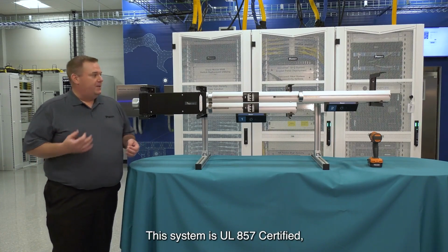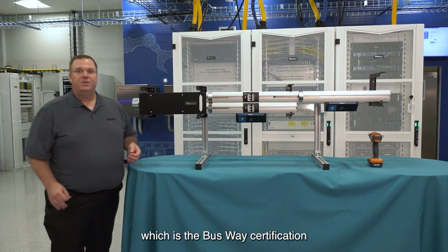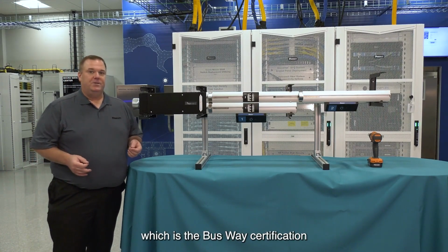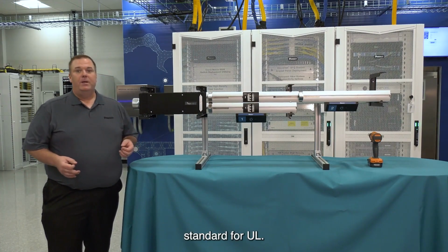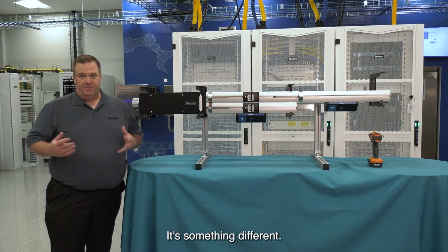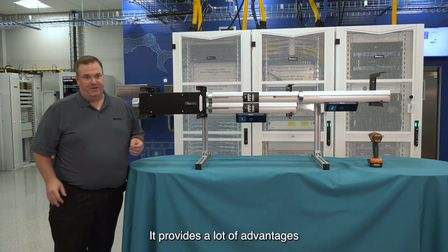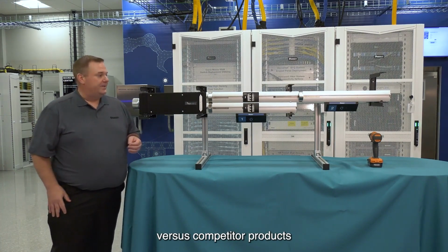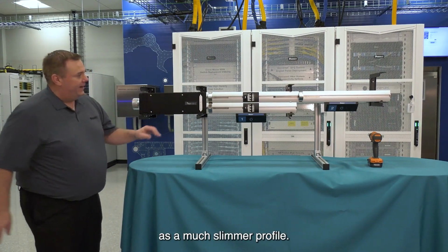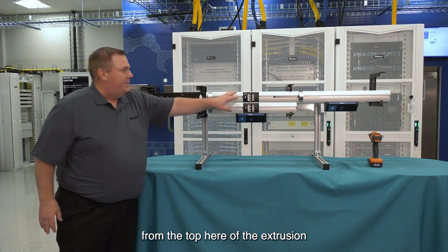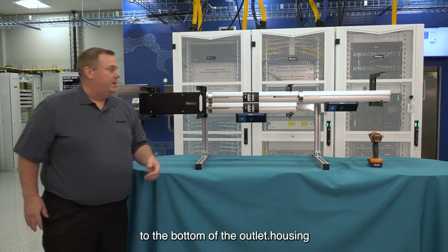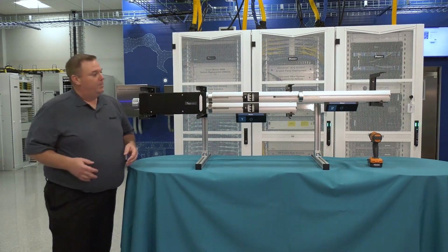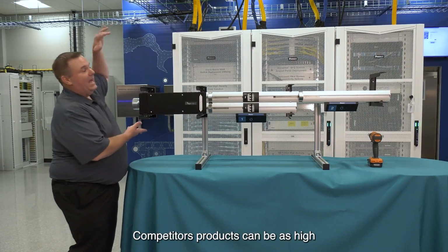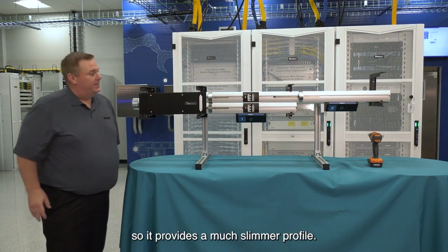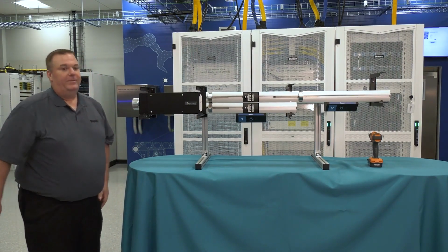This system is UL 857 certified, which is the busway certification standard for UL, but it is not a busway. It's something different. It provides a lot of advantages versus competitive products. It has a much slimmer profile. It's 9 inches from the top of the extrusion to the bottom of the outlet housing. Competitors' products can be as high as 30 inches, so it provides a much slimmer profile.